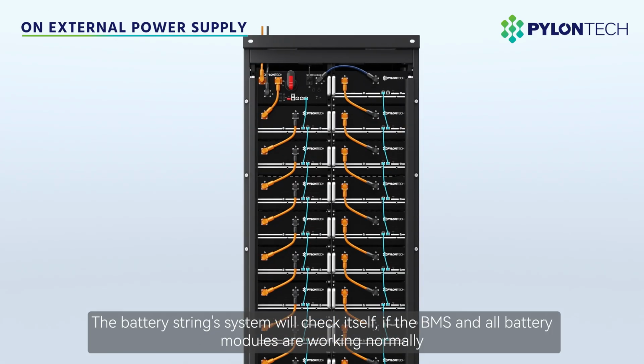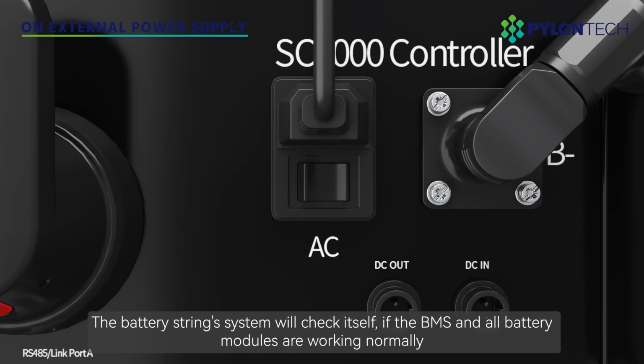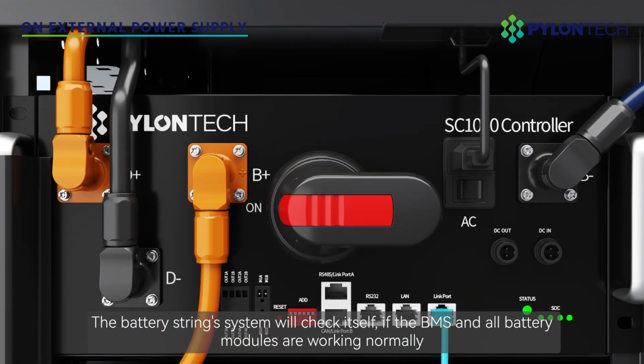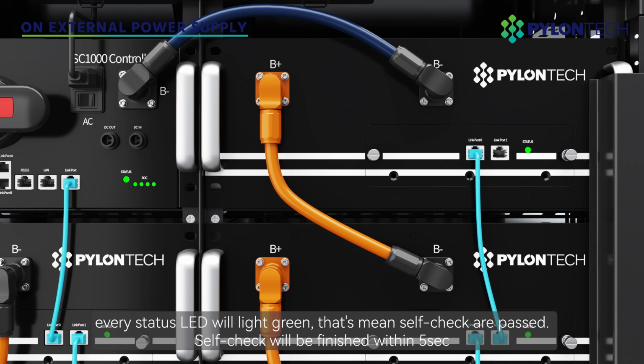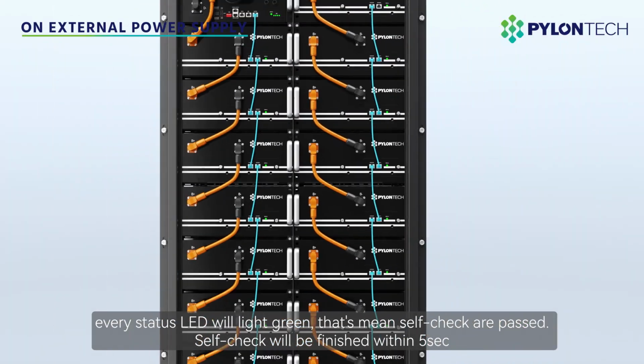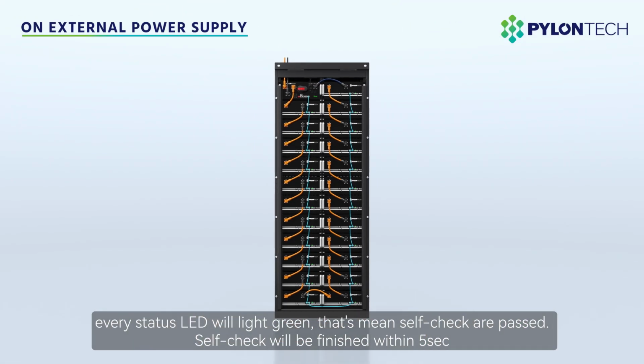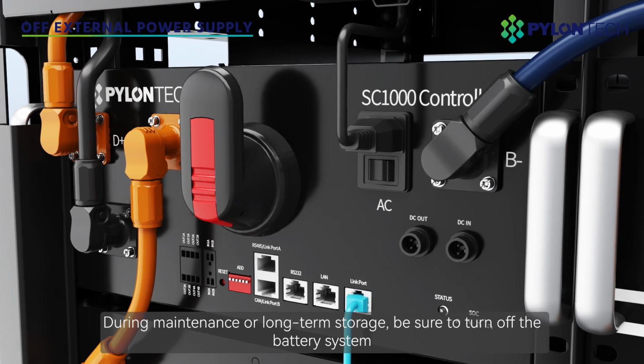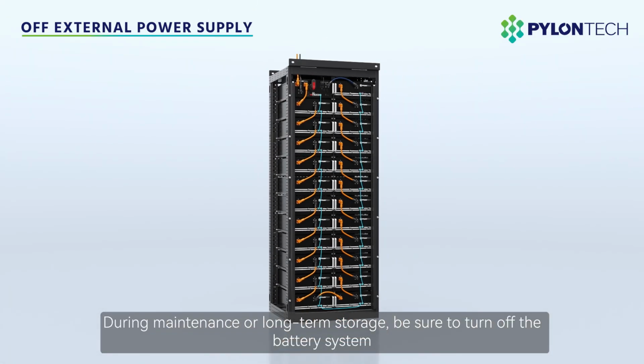The battery strings system will check itself. If the BMS and all battery modules are working normally, every status LED will light green. That means self-check is passed. Self-check will be finished within 5 seconds.